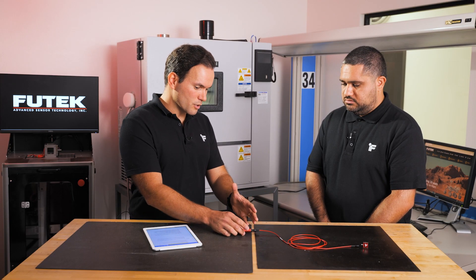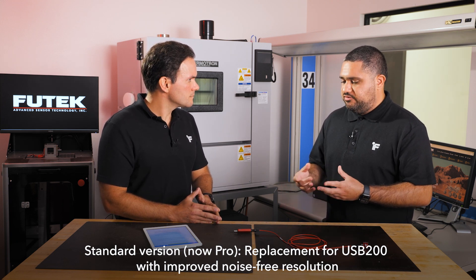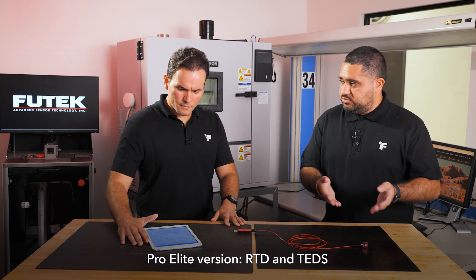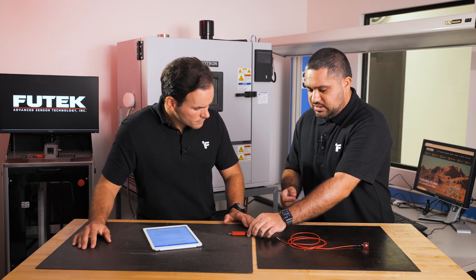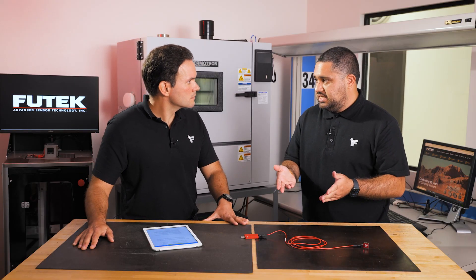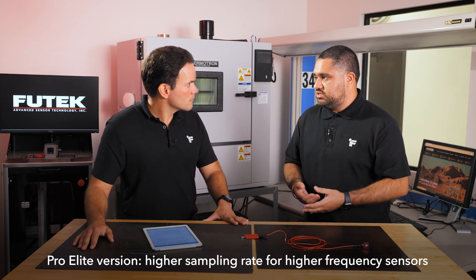This product has two versions: the standard version and the pro version. The standard version was designed as a replacement for the original USB200, supporting similar sampling rates but improved to 20 bits noise-free resolution. The pro version adds features such as RTD for temperature compensation and TEDS support — where connecting a sensor automatically triggers TEDS readback and self-calibration. The pro also supports the higher sampling rate, making it suitable for sensors with higher natural frequencies and applications like drop tests.